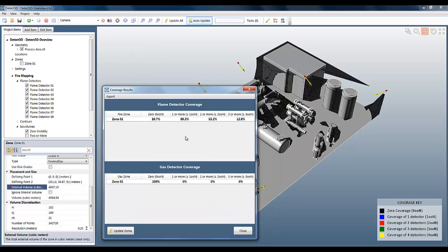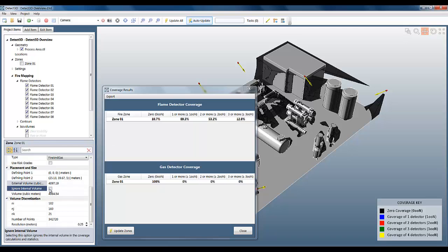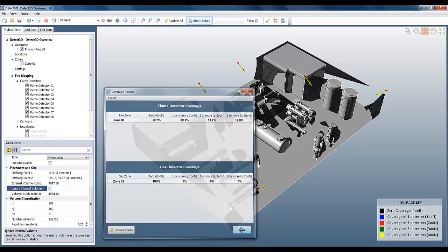If we like, we can choose to ignore the internal volume calculation. In other words, we can assume the fire zone is completely open. The statistics automatically update. And when the internal volume calculation is ignored, the zero visibility goes from 10% right up to 26%. So you can see that it's very important to take into account this internal volume calculation.